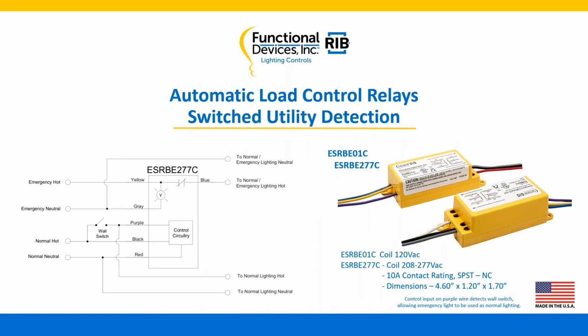Here we'd like to show you an automatic load control relay with a switched utility detection. This is an earlier device. We still sell a few of them, and we're very proud of them. But as we move on, we find that there are other avenues out there, other products that we're moving to make and passing along these. Simply, how they work is basically monitoring this wall switch over on the left-hand side. This is the application. It monitors because these are up in the actual ballast channel, so some way it has to know what's going on with that switch. So it's monitoring is what it's doing. When the normal power drops, the emergency power kicks on, and our product basically takes over control and brings that fixture to full brightness.